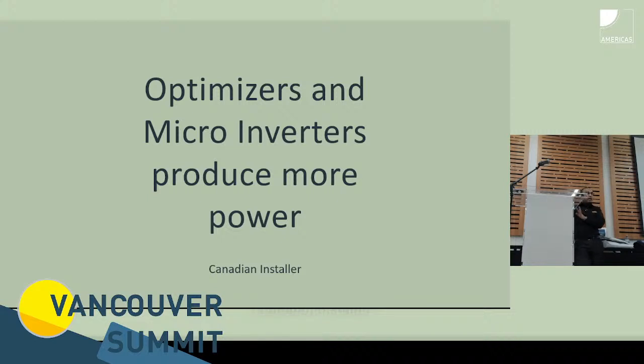So you're already oversizing them, correct? Which means that even if I were to drop the optimizers out of the picture during the sun hours, basically summer, assuming the system's designed for peak summer, your PV panel is still capable of giving 15 kilowatts worth of DC, and with a 10 kilowatt inverter I can still get my 10 kilowatts without the optimizer because I've so overpowered the system. So using that argument, come back to the times of year when you'd actually expect to see any value from either an optimizer or a microinverter. Which part of the year would that be?